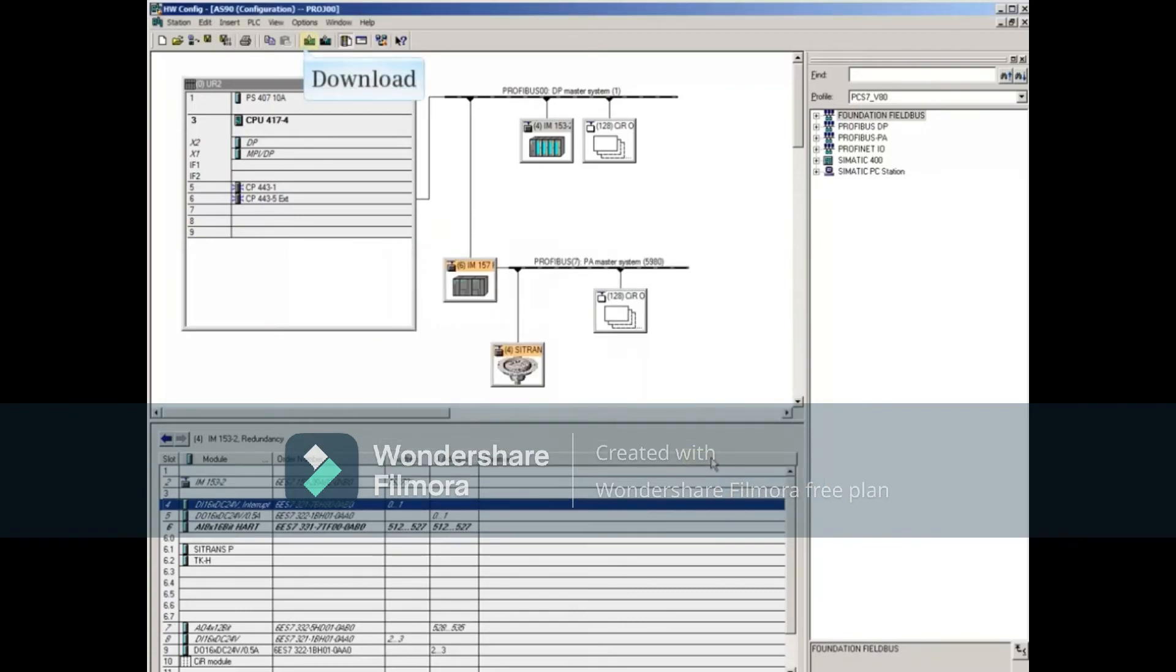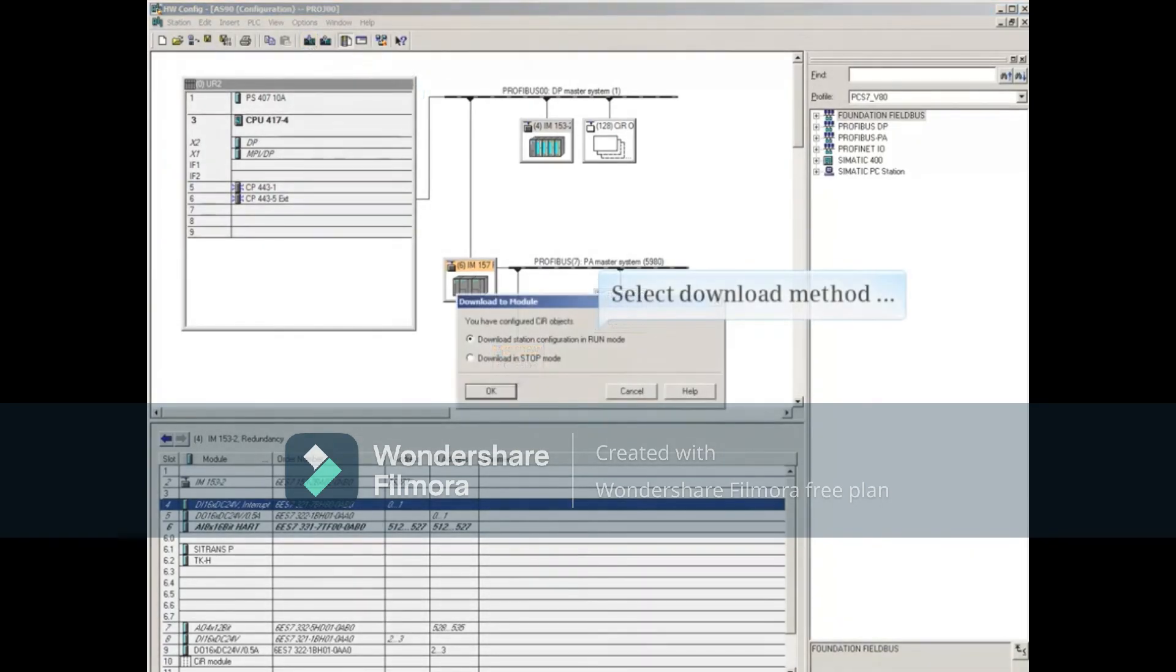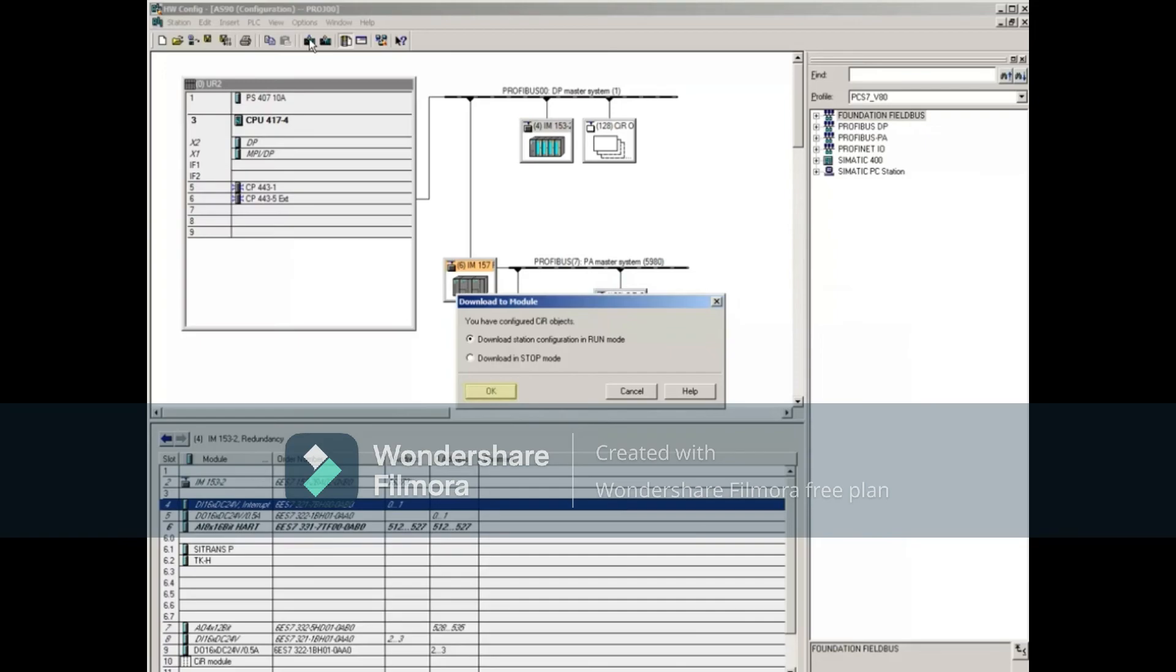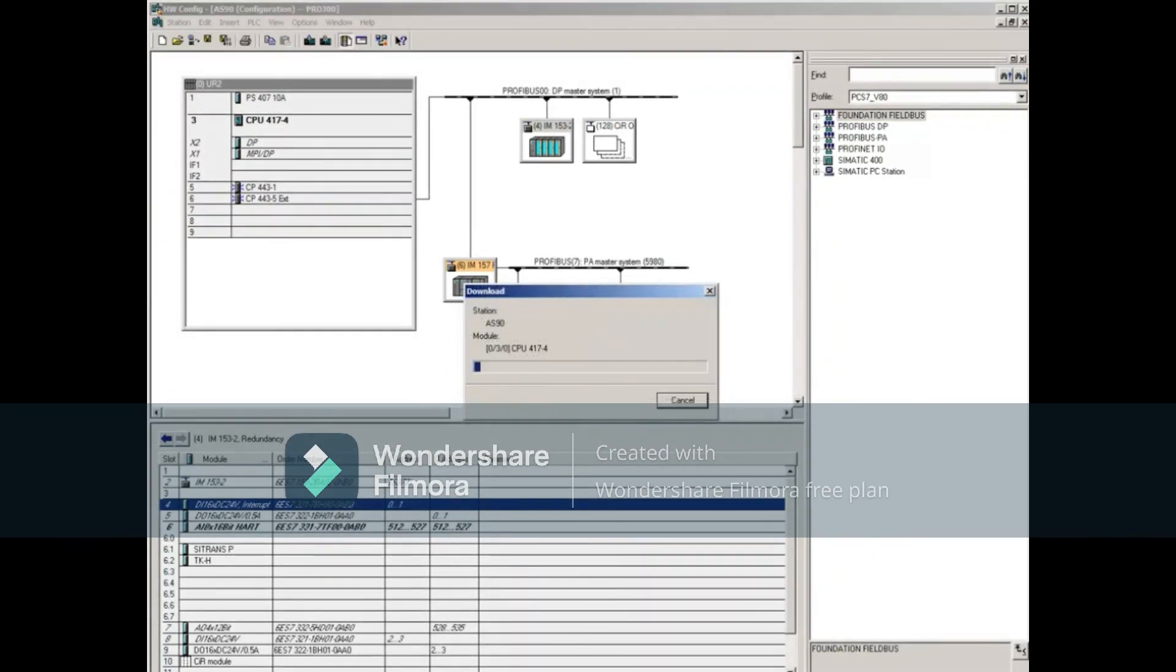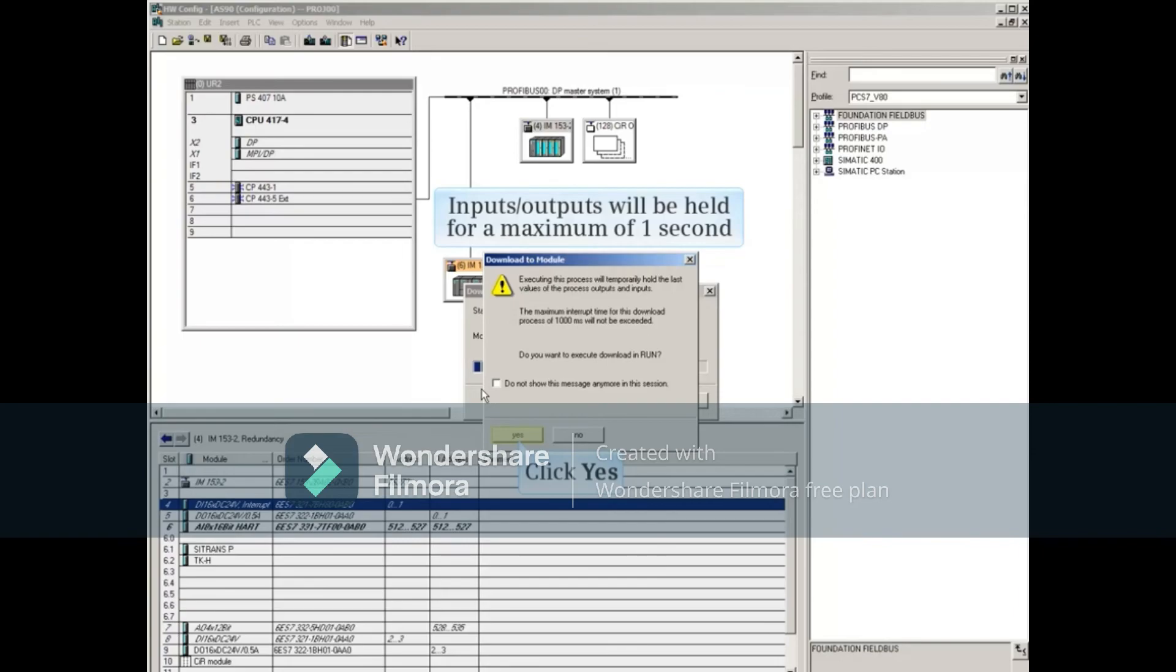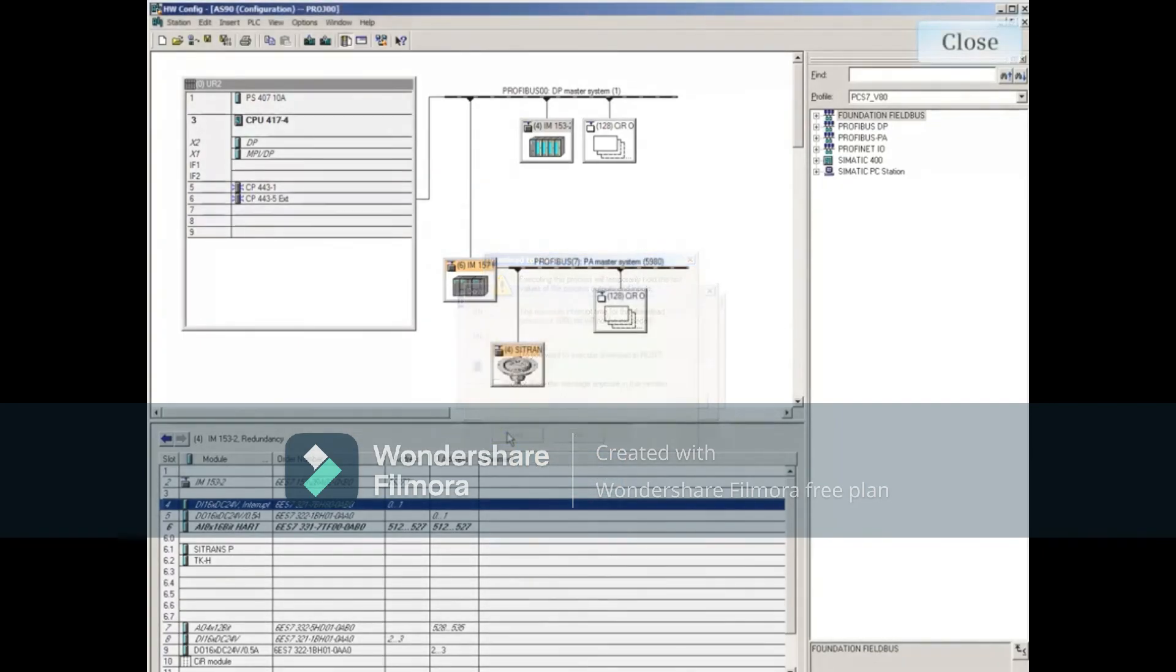Now you can download the Hardware Configuration change. If you have CIR configured, you can download in Run Mode. Read and acknowledge the warning indicating that the last input output values will be held for a maximum of one second. This is typically much shorter. Close Hardware Config.